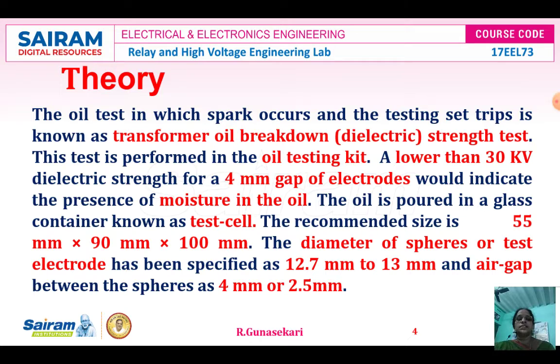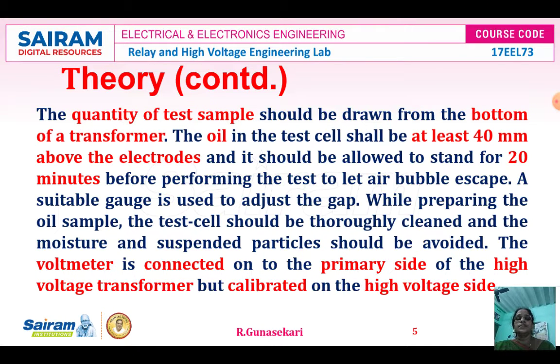The recommended size is 55 mm by 90 mm by 100 mm. The diameter of the sphere or test electrode has been specified as 12.7 mm to 13 mm. The air gap between the sphere-shaped electrodes is 4 mm or 2.5 mm. The sample for the test cell should be drawn from the bottom of the transformer tank. The oil in the test cell shall be at least 40 mm above the electrodes. It should be allowed to stand for 20 minutes before performing the test to let air bubbles escape.